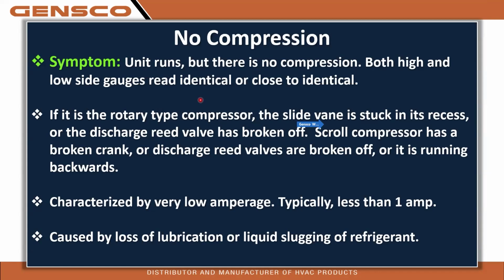The second failure type could be a no compression symptom. Unit runs, but there's no compression. Both your high and low side gauges are reading identical, or close to identical. If it's the rotary type compressor, the reason for this would be the slide vane stuck in its recess, or the discharge reed valve has broken off.